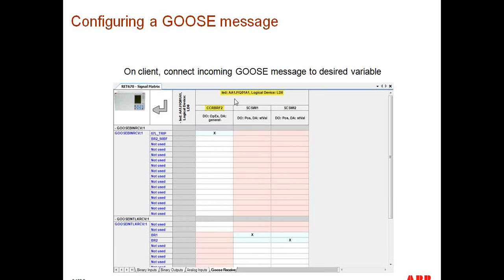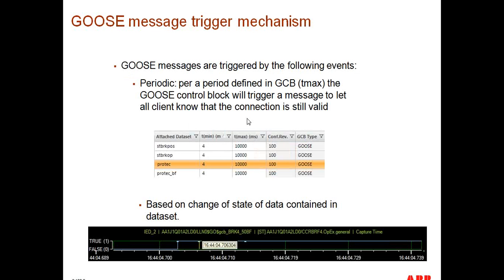This is just the way it's represented inside PCM 600, so that there is an understanding that that piece of information is coming from this device. And by the way, it is pretty straightforward to see that this is a breaker fail trip function. It's pretty straightforward to determine that this is the position of this breaker, and this is the position of this breaker. I can understand that because of the logical node naming convention, RBRF, in this case CSWI for controller of circuit breaker, and then I can see that they're sending POS.